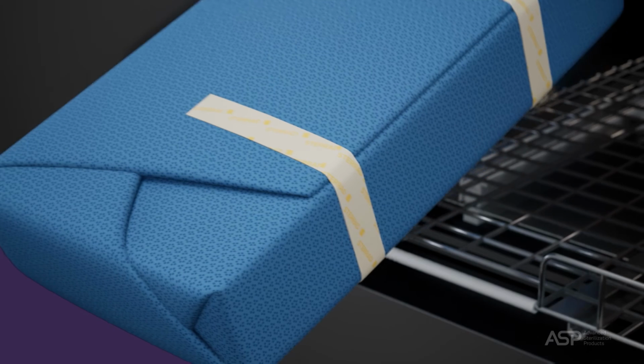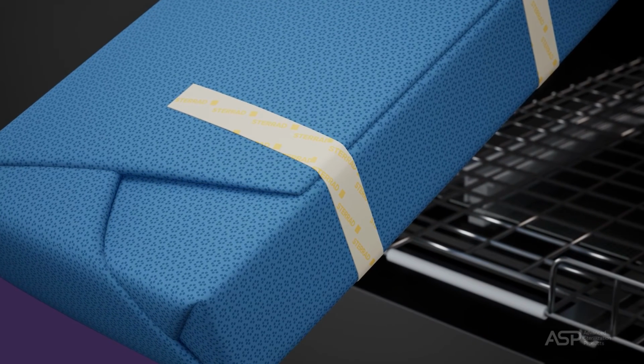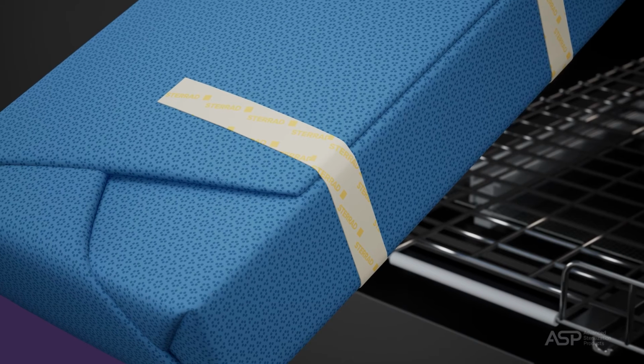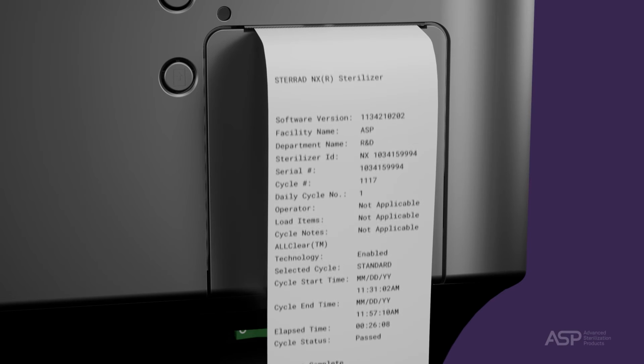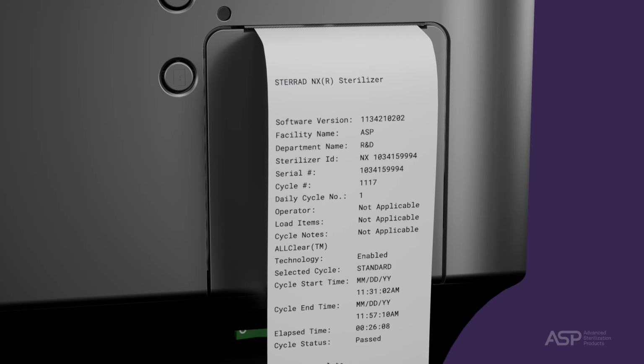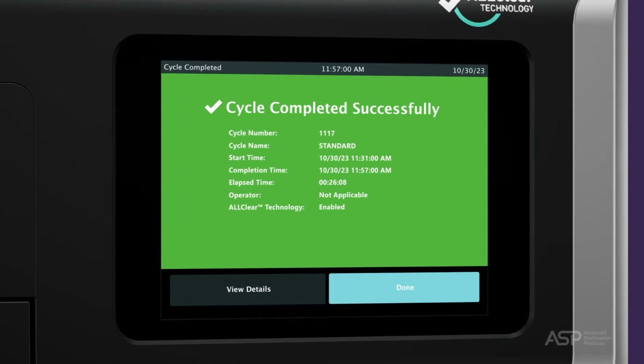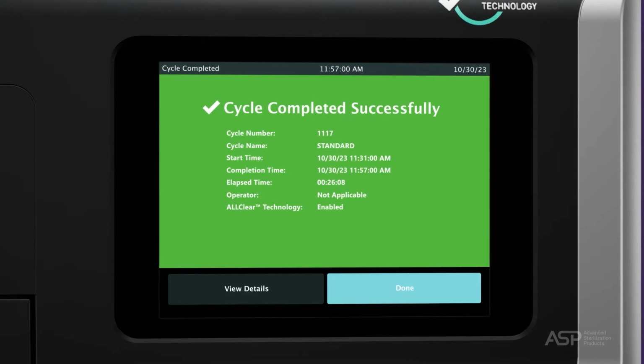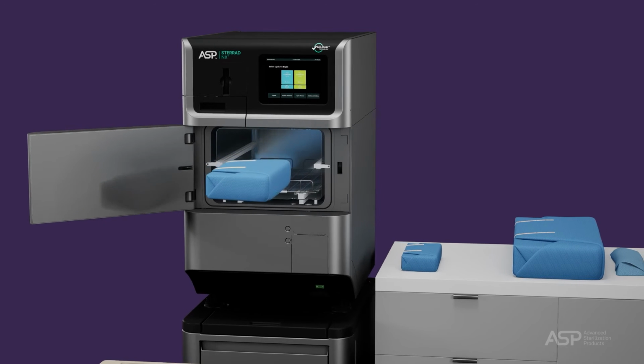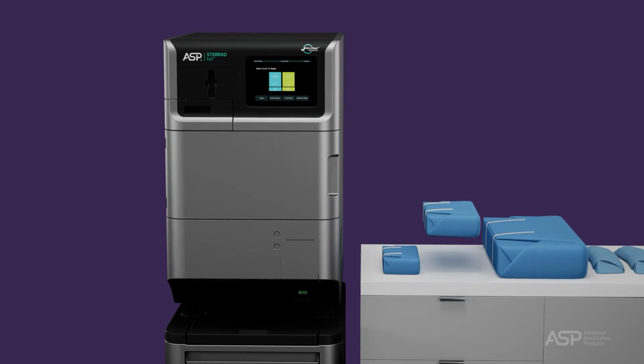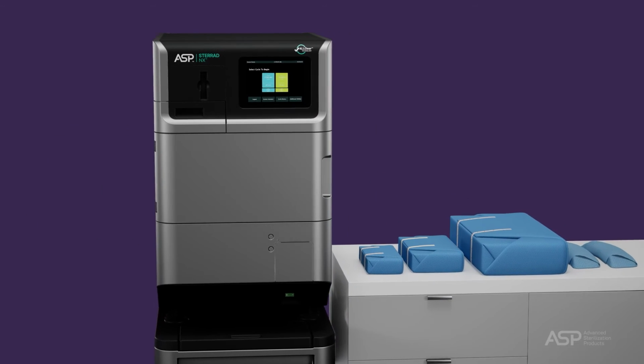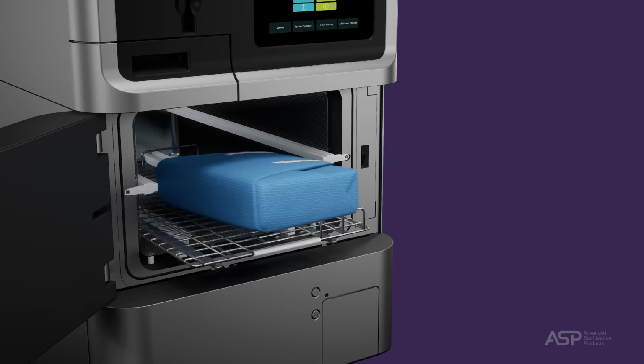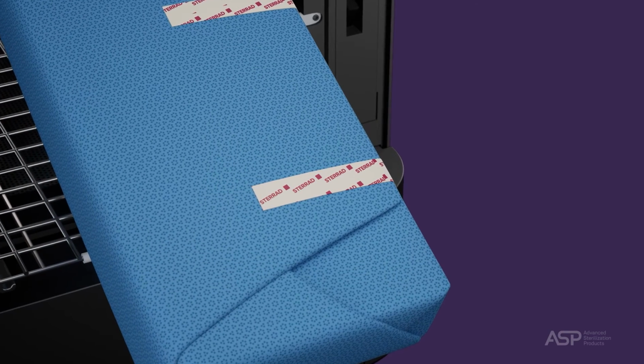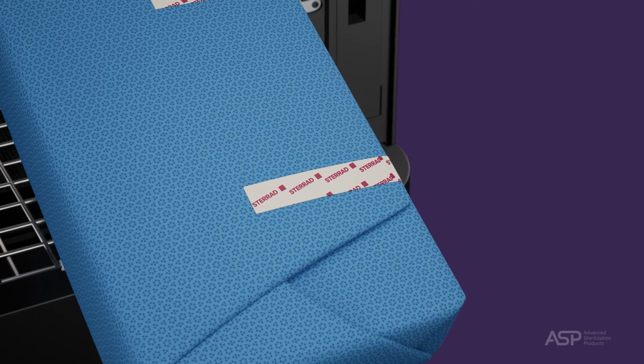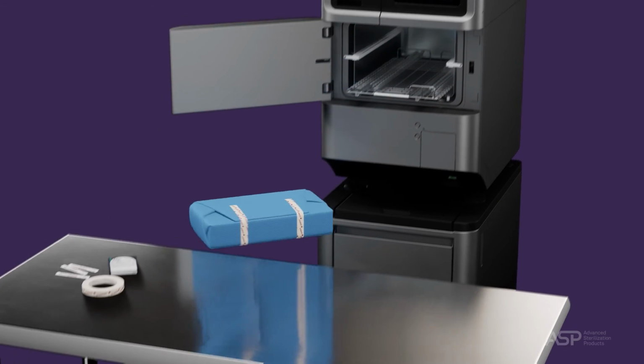Ensure that the chemical indicators on or in the sterilized packages exhibit the correct color change, and that the cycle printout shows that all parameters were met. Additionally, the system screen will display the cycle status as process complete. The load is now ready for immediate use. Follow your hospital or healthcare facility's policy. If the chemical indicators do not exhibit the correct color change, investigate the cause, repackage the devices, and reprocess.